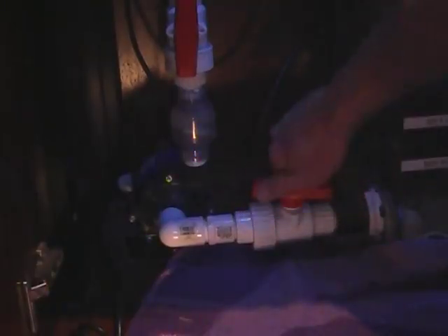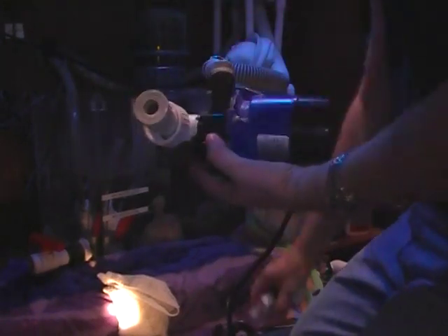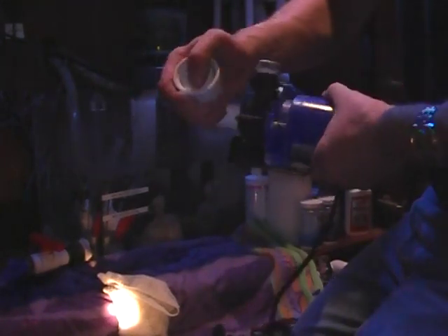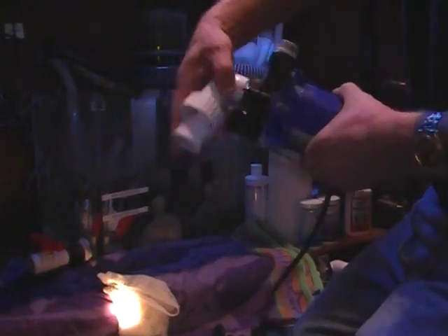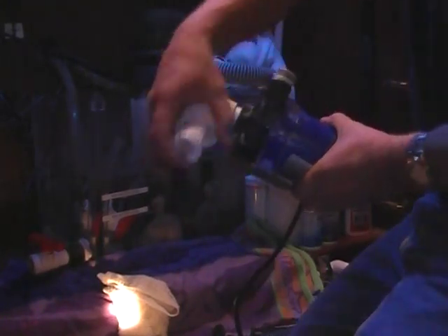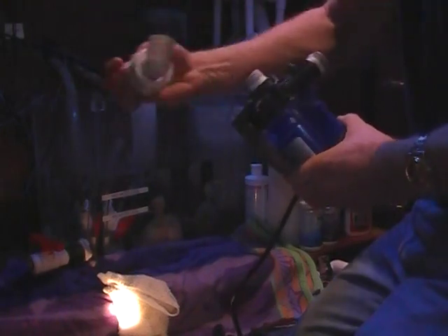Upon arriving, we've confirmed the problem is, in fact, the water pump. But there's a second issue: the union ball valve on the inlet side isn't closing. This is the whole point of the union fittings — quick and easy removal of the pump. With a little jiggling, it appears there's some debris caught in that union ball valve. We've been able to remove the pump, and with a number of towels, we'll catch the small amount of water slipping out of the filter.